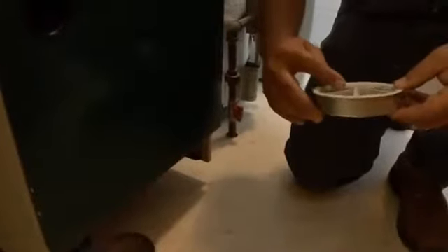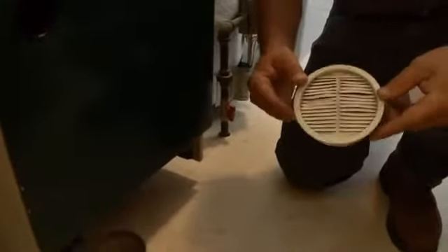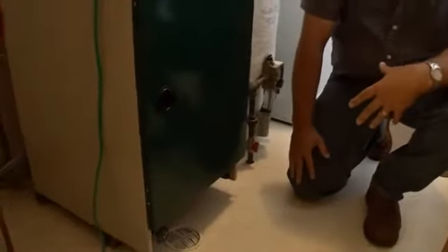The combustion air for this actually comes in through this little area right here, and we have this grill here which doesn't allow for very much air. The actual free area on this is minimal, as you can see. It doesn't meet the National Fuel Gas Code as far as the combustion air for this room. This is definitely going to be short the proper amount of combustion air for this room.